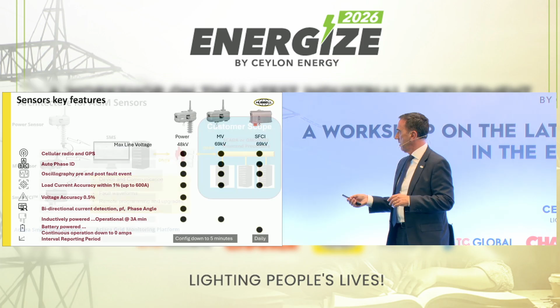What we're showing here is that a big amount of events are not outages. 84% are line disturbances, something that happens on the line but isn't a fault - you don't disconnect the line, but something is happening and you don't know why or even that it's happening. With the line sensor, you get this information that something is happening on the line. Some of these we call momentary.